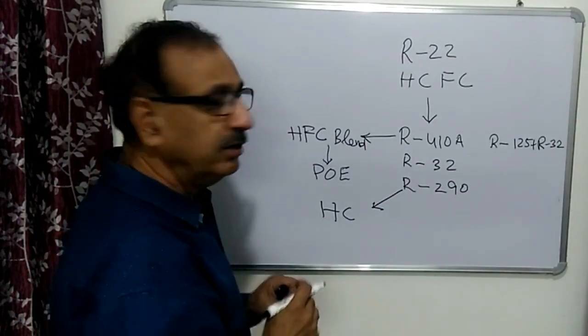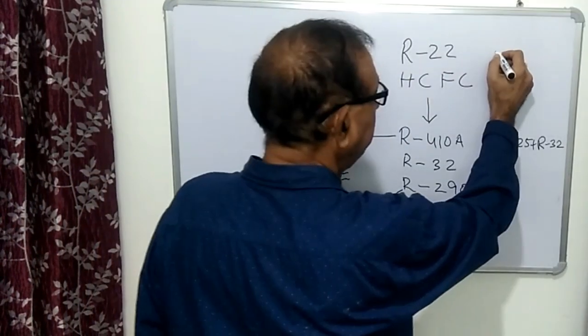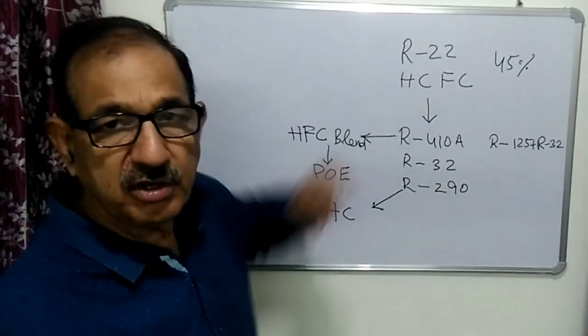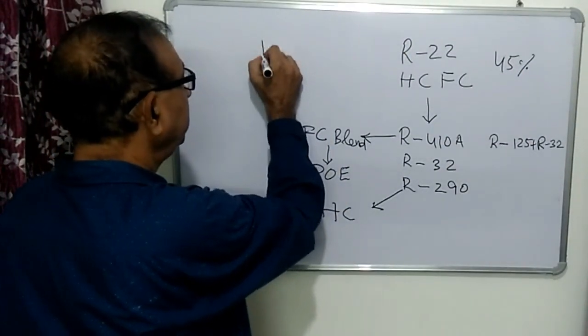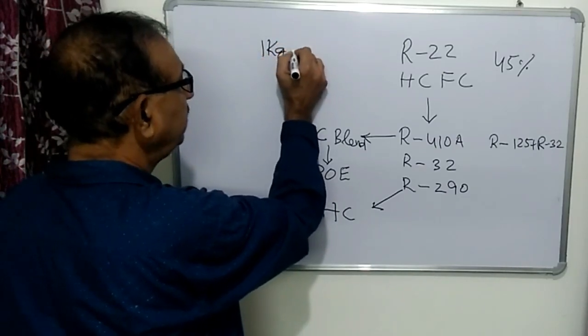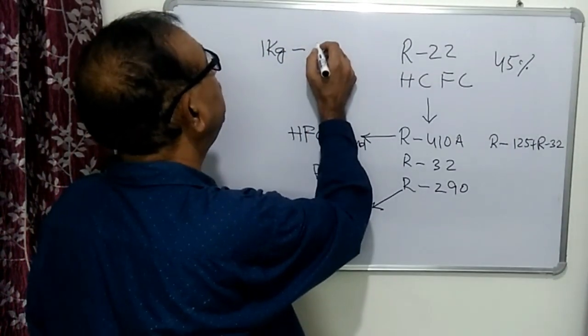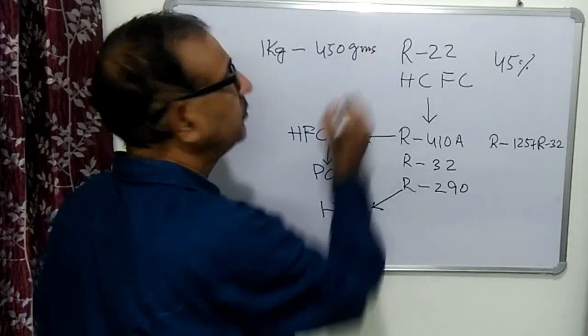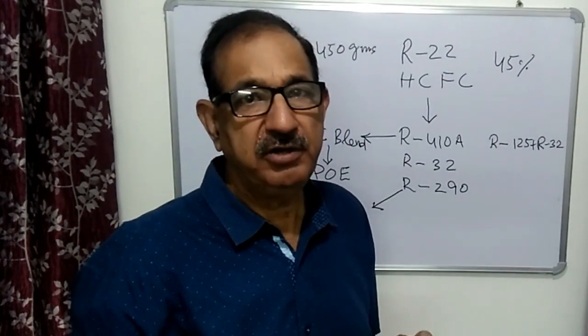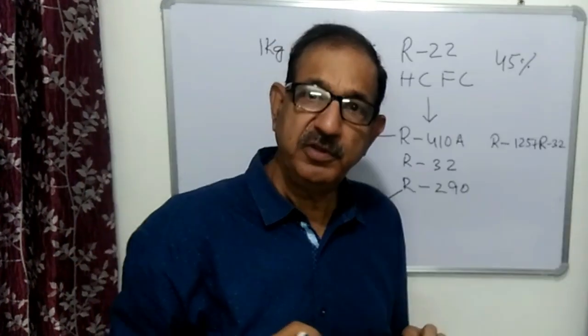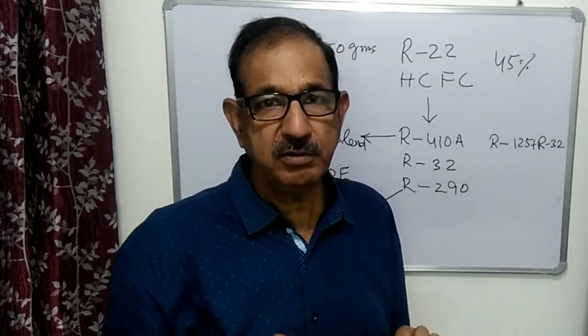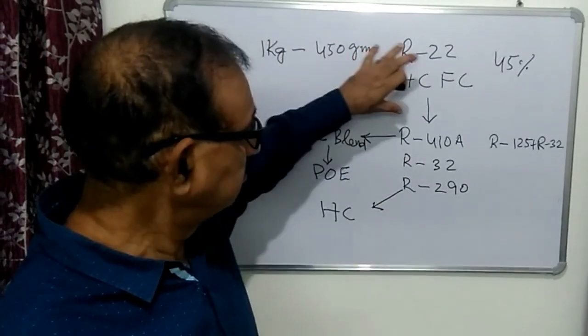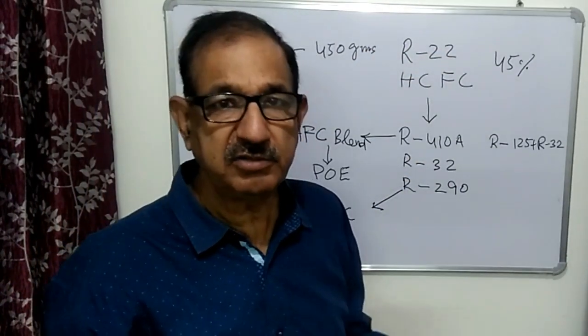The charge quantity restriction for R290 is a maximum of 450 grams in a domestic air conditioner. If we are replacing R22 with R290, we have to charge only 45% of the R22 charge quantity. So if we had charged 1 kg of R22, we need to charge only 450 grams of R290.